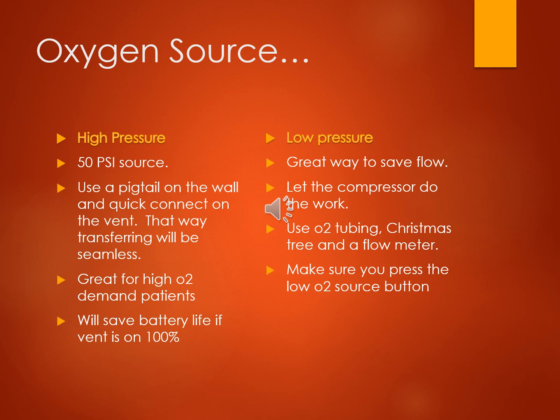The compressor, actually on this one, is a turbine. The turbine is going to generate flow, like compressed air for the ventilator, and then you bleed your FiO2 in normally. But if you're using a 50 psi source, you're giving it what it needs, and then you wouldn't have to blend that much in.